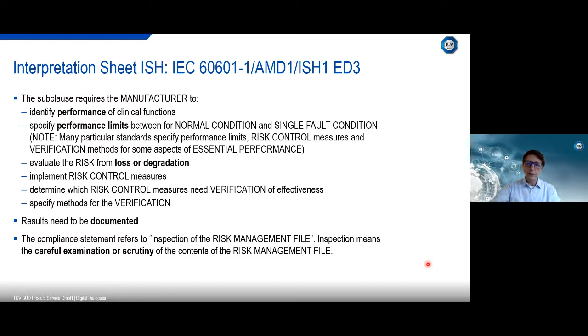The results of this assessment have to be documented. And the compliance statement, this is then important for a test lab, refers to the inspection of the risk management file, and inspection means careful examination or scrutiny of the contents of the risk management file. So the test labs have to have a close look at these documents which are published by the manufacturer with respect to this single fault condition of essential performance.